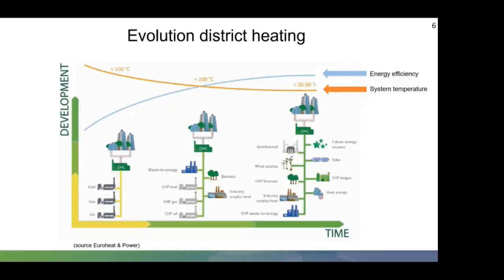Over the years, the heat sources changed and combined to give more efficiency, greener solutions and provisions for heat to the network. If we look closely at the evolution of the heat networks, you can see the integration of technology and reduction in circulation temperatures. Originally you're looking at 100, 140 plus, really high temperatures, and over the years the temperatures are slowly dropping, but the energy efficiency is growing. The integration of insulated pipes, especially plastic and polymer pipes. Then you've got the integration of waste to energy plants, geothermal, wind turbines, CHP of biomass, industry waste, heat pumps, solar, CHP. So everything could be added into the district heat network to try and make the system as efficient and low temperature as possible.